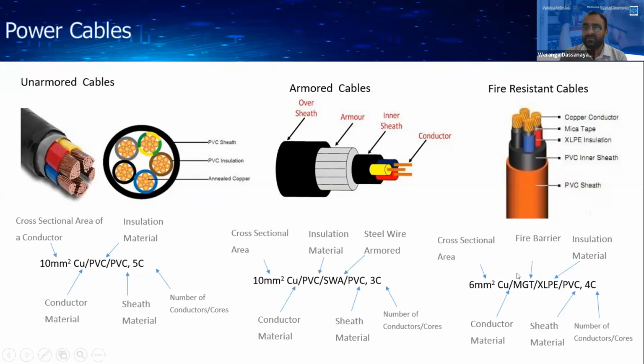So the difference between these fire resistant cables and normal power cables is that after the conductor, there is a fire barrier. Most probably this will be MGT, that means mica glass tape. This material is a very fire resistant material. If you put this mica glass tape on a flame, it will not burn. So this material is used to protect this cable from a fire situation.